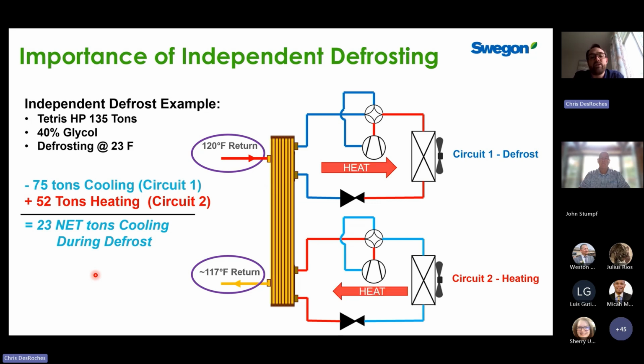If we have an air-cooled chiller that's running, right? We take a 100-ton chiller, we rate that 100-ton chiller at 95 Fahrenheit ambient. But we don't defrost when it's 95. We defrost when it's 35, 32, 23 ambient outside. So you have to ask yourself, what happens to the capacity of an air-cooled chiller as it gets colder outside? Does its capacity go up or does its capacity go down? Capacity increases, it becomes a lot more efficient at rejecting the heat. It's running at lower condensing pressures, so we get a lot more capacity out of it.